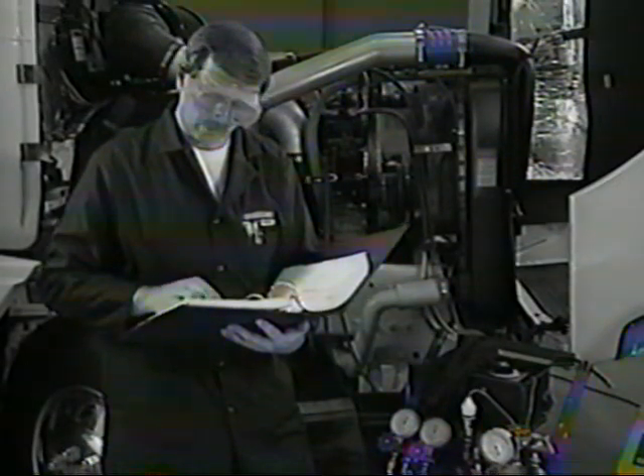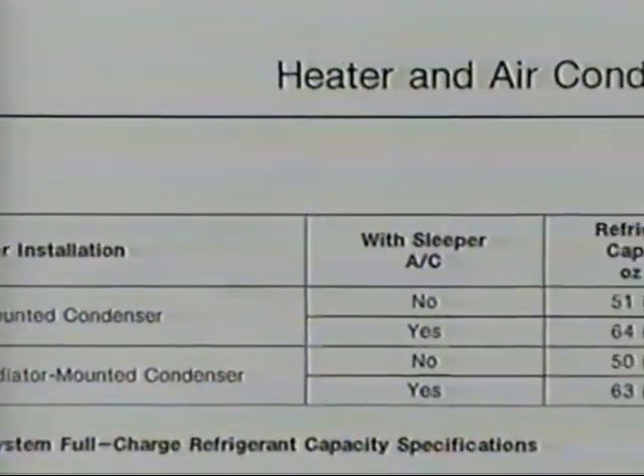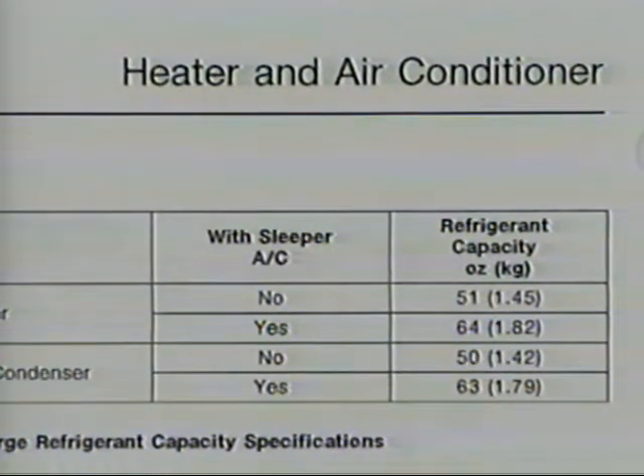2 basic methods are available: liquid charging and vapor charging. Before beginning either process, check the specifications tables for the required refrigerant quantity. Weigh the bulk container or use a graduated dial for a bulk container with a heater. Filling the container and turning on the heater during evacuation will speed the process. Be careful not to overheat the refrigerant. When liquid charging, open the container liquid valve and the manifold high side hand valve. Caution: do not open the manifold low side hand valve or start the engine while liquid charging, or the compressor could be damaged. When the system is fully charged, close the manifold high side hand valve and turn off the refrigerant supply to the manifold set.